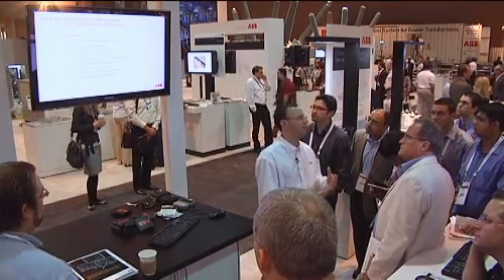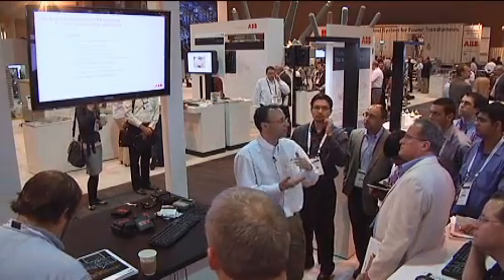You have to be able to monitor your performance to make sure you're actually achieving your objectives. We often will provide a service to customers, to utilities, to do an analysis of their VAR losses prior to us deploying a volt VAR management system. So you can run this analysis, see your losses prior to it, and determine that you have enough losses to warrant the system, which is typically the case if you don't already have some form of volt VAR management system.